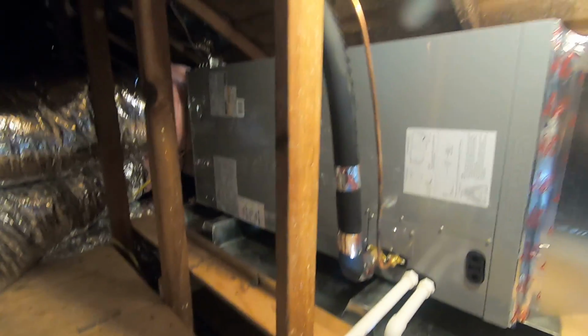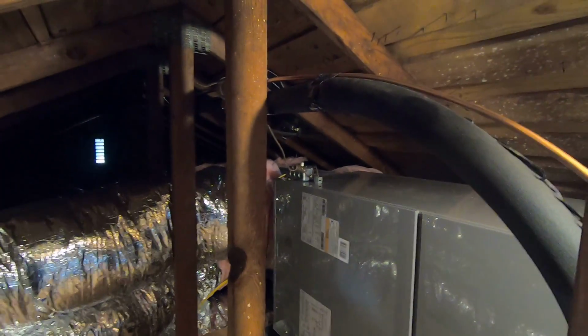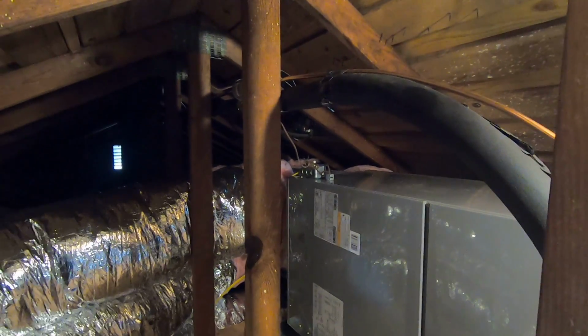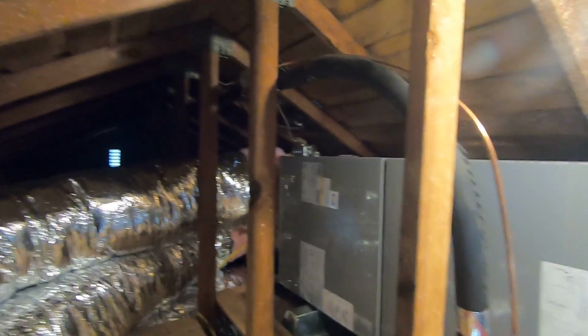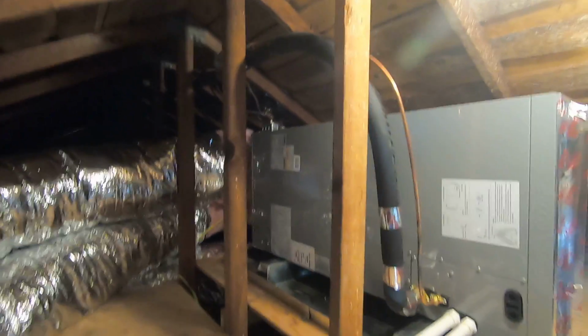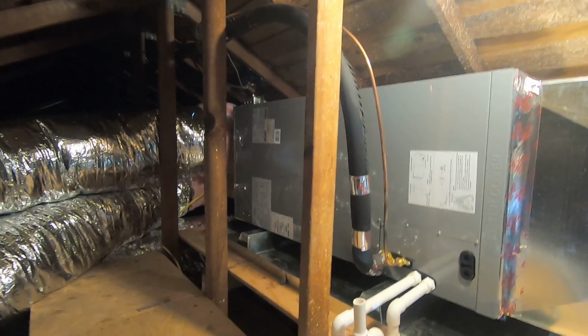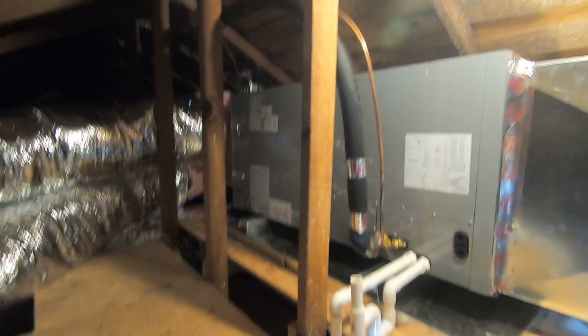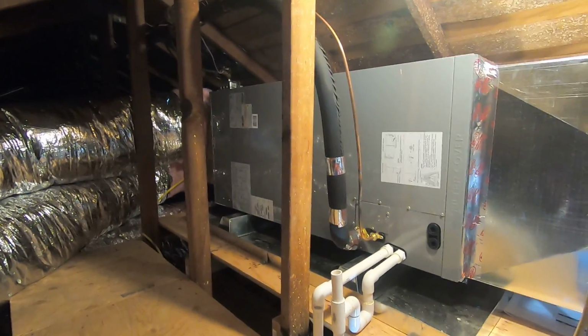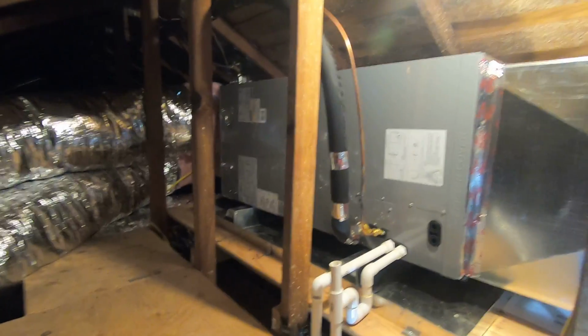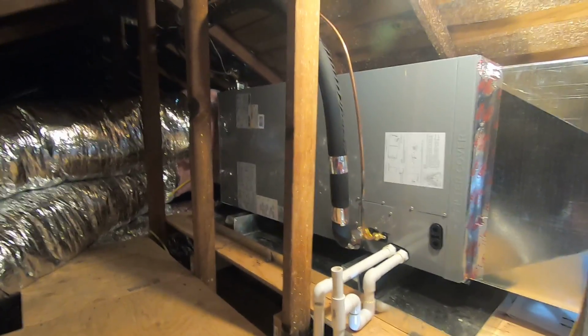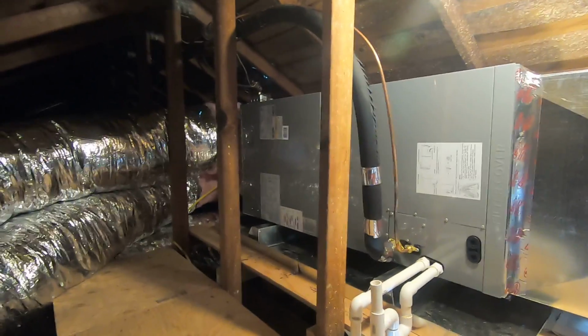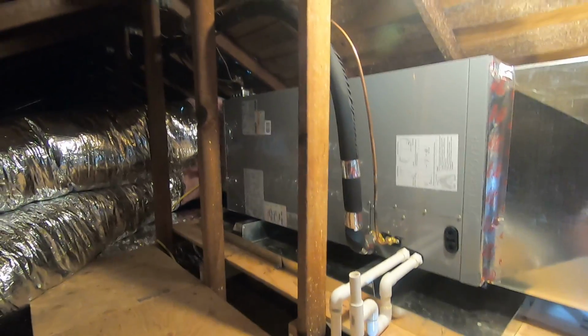To get the electrical up here, we came off the main panel, and you can see on top of the unit over there we have a disconnect switch. So from the main panel we had to run a dedicated circuit for this fan coil in the attic. It cannot tee off and go anywhere else, so it is dedicated. It's a 20 amp 2-pole breaker in the panel, and then we ran number 12 wire up here to power the unit. Then we have all the ductwork that we did.